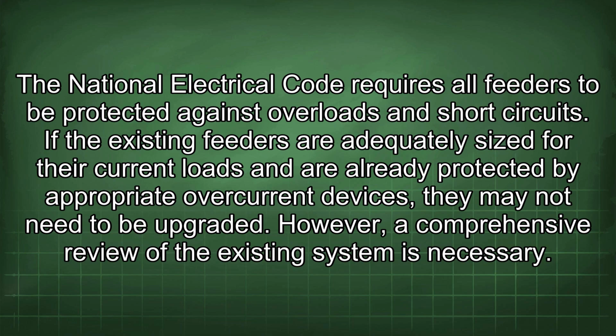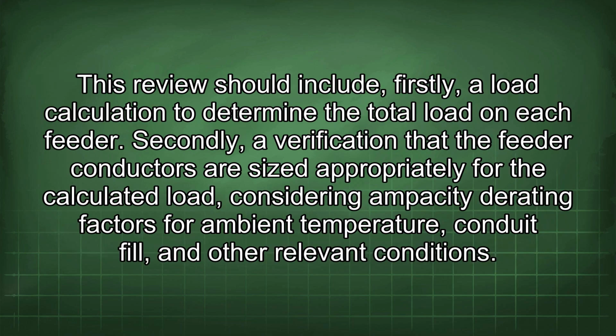If the existing feeders are adequately sized for their current loads and are already protected by appropriate overcurrent devices, they may not need to be upgraded. However, a comprehensive review of the existing system is necessary. This review should include, firstly, a load calculation to determine the total load on each feeder. Secondly, a verification that the feeder conductors are sized appropriately for the calculated load, considering ampacity derating factors for ambient temperature, conduit fill, and other relevant conditions.